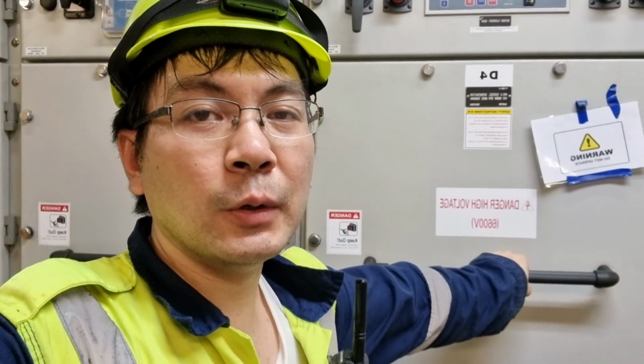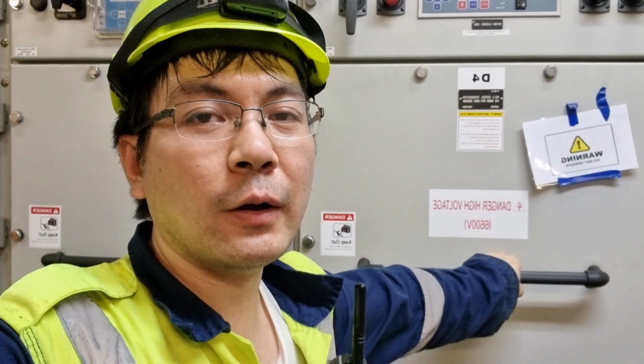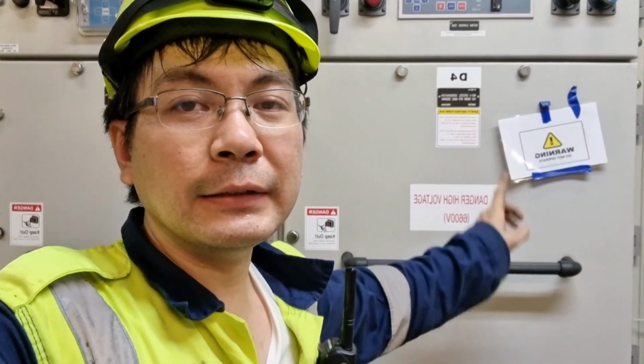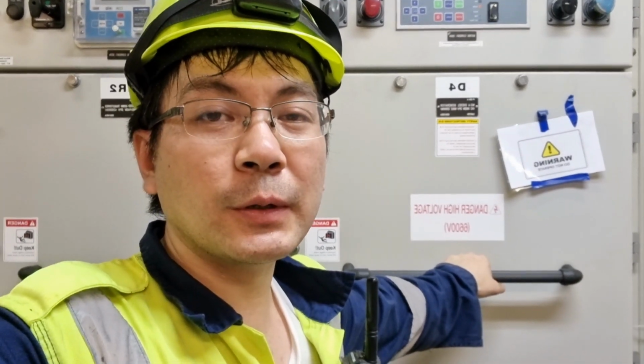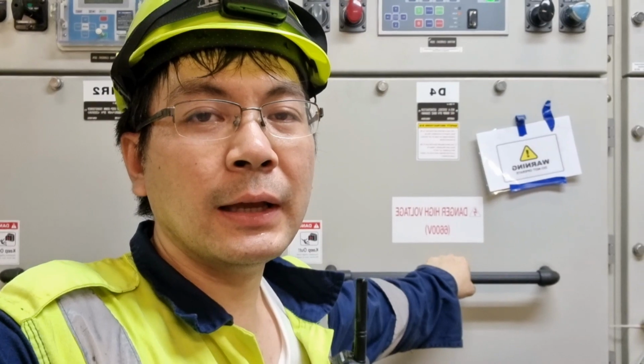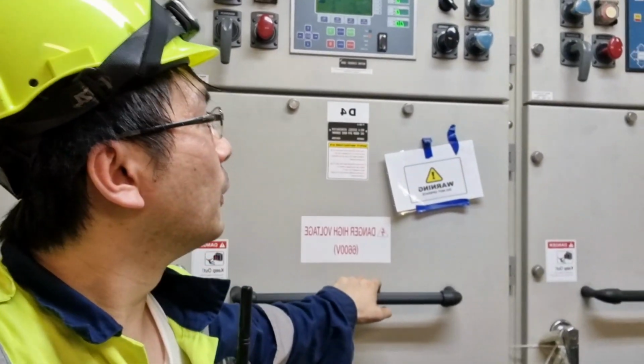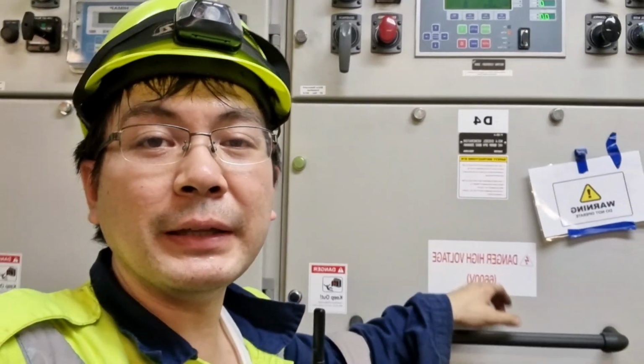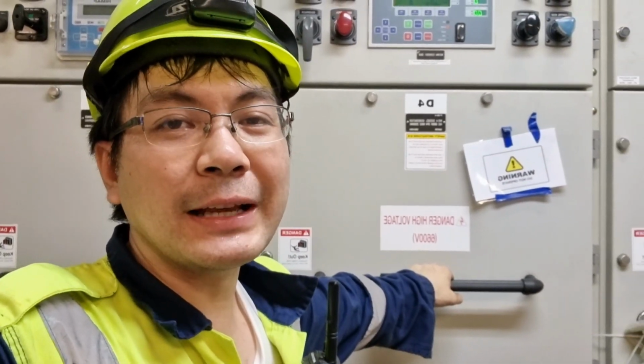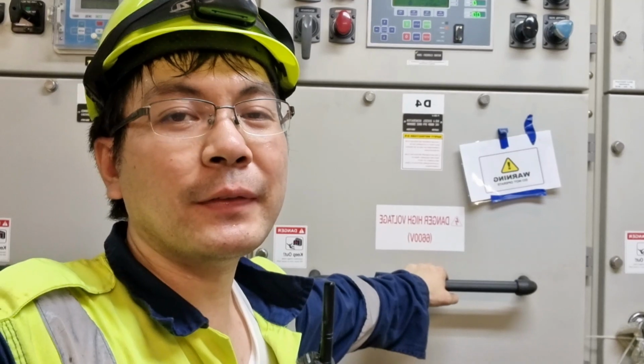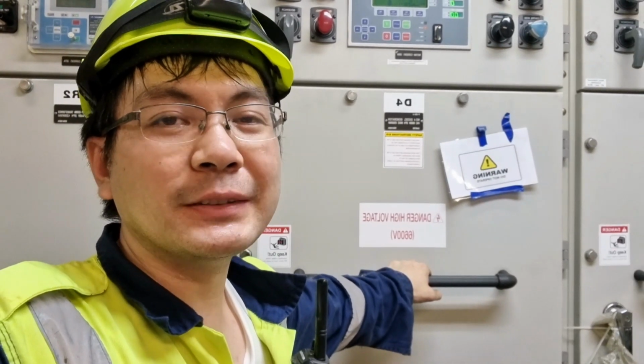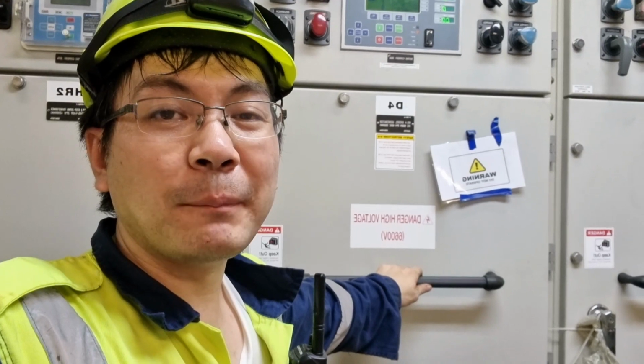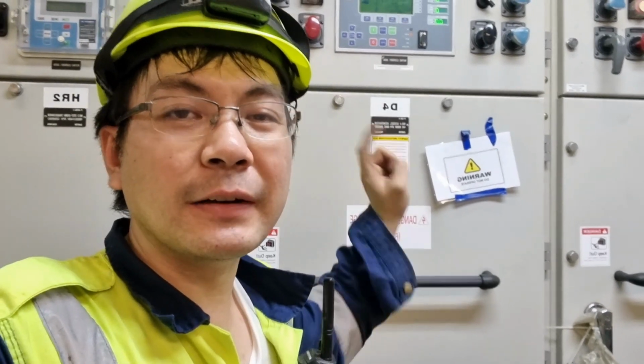During the testing, we cannot start the generator on the local control panel or remotely. We were only able to start the generator through the emergency start. Because of this, we know for sure that there is also a mixed wiring. And the worst about this one is we cannot change the speed of the generator. So it looks like we will have part number 3 of this generator cable tracing. So come and join me in part 3 of this cable tracing of our generator number 4.